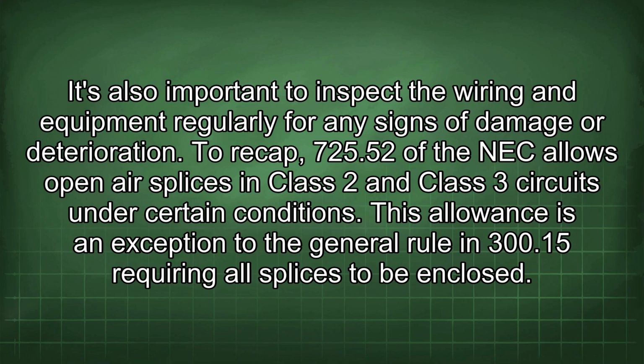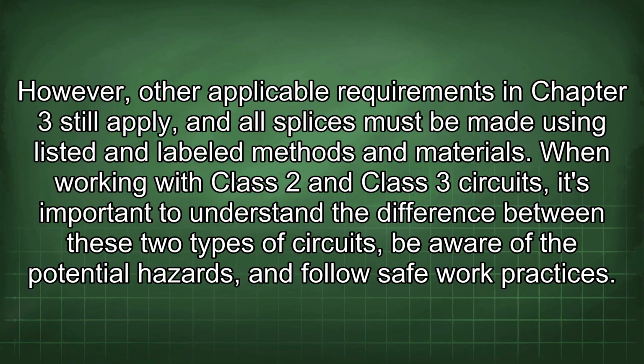To recap, 725.52 of the NEC allows open-air splices in Class 2 and Class 3 circuits under certain conditions. This allowance is an exception to the general rule in 300.15 requiring all splices to be enclosed. However, other applicable requirements in Chapter 3 still apply, and all splices must be made using listed and labeled methods and materials. When working with Class 2 and Class 3 circuits, it's important to understand the difference between these two types of circuits, be aware of the potential hazards, and follow safe work practices.